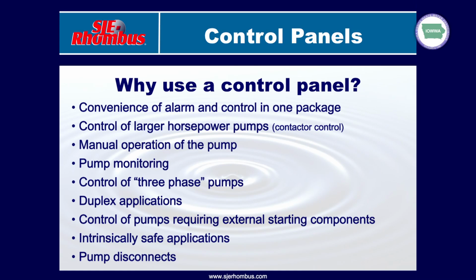And then intrinsically safe applications. When I refer to intrinsically safe, a lot of times municipally or commercially, you're going to have an engineer that's going to require an intrinsically safe control panel. Basically, intrinsically safe is going to isolate anything that could potentially generate a spark that could ignite combustible gas. It's going to isolate it in a compartment of the panel away from where that combustible gas could be occurring. And so if it's an intrinsically safe requirement sized by the engineer, a control panel is the only way to go about getting that requirement met.